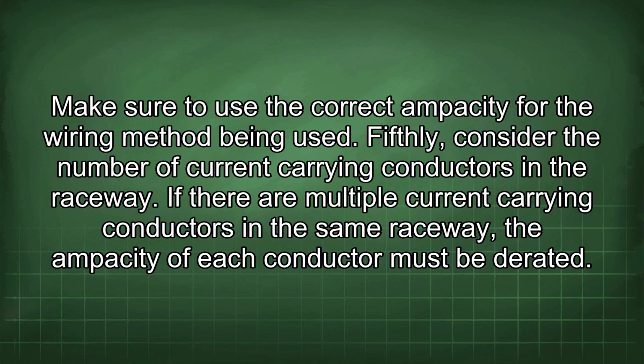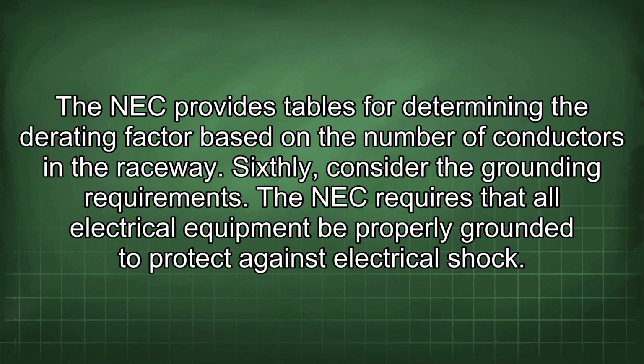Fifthly, consider the number of current-carrying conductors in the raceway. If there are multiple current-carrying conductors in the same raceway, the ampacity of each conductor must be derated. The NEC provides tables for determining the derating factor based on the number of conductors in the raceway. Sixthly, consider the grounding requirement. The NEC requires that all electrical equipment be properly grounded to protect against electrical shock.